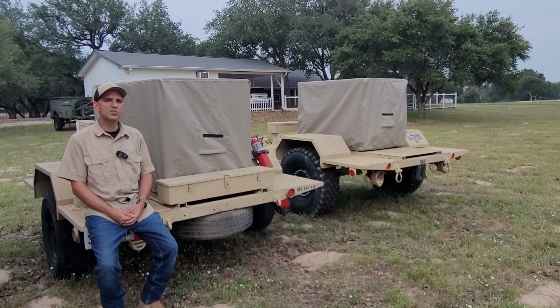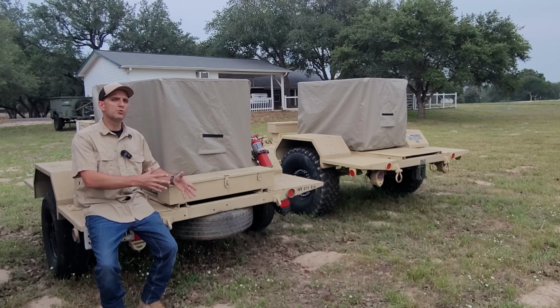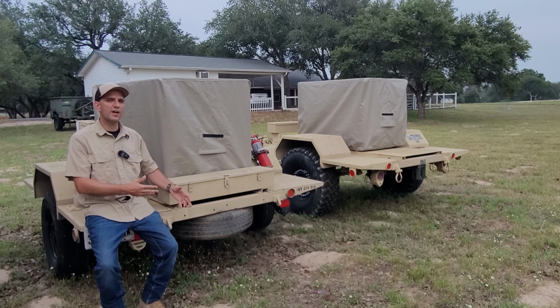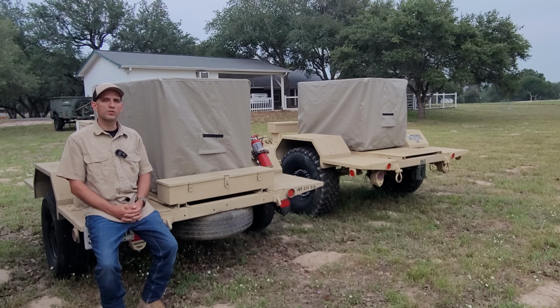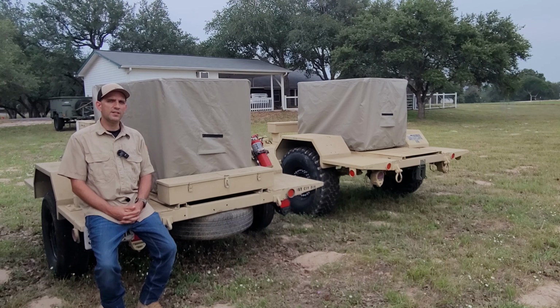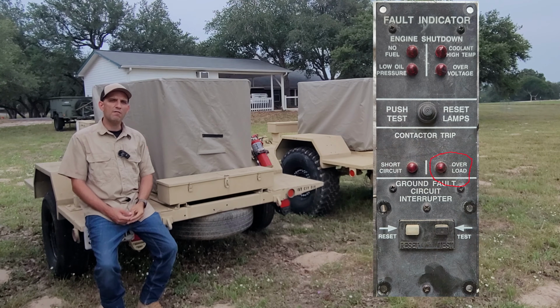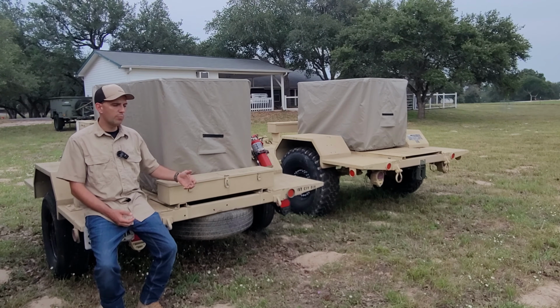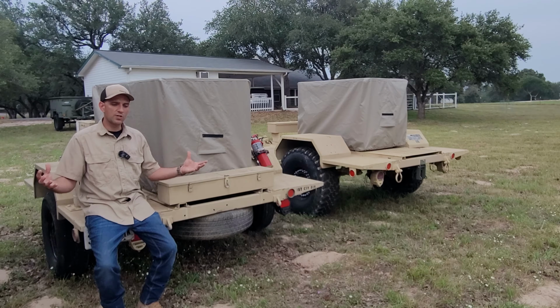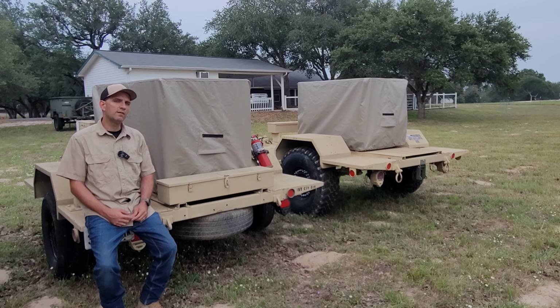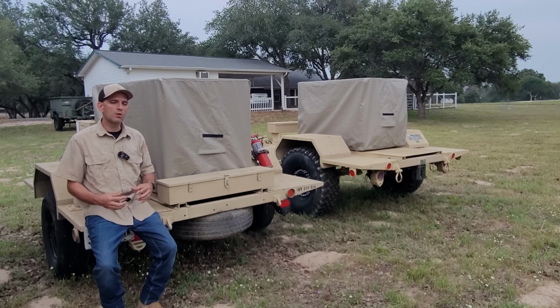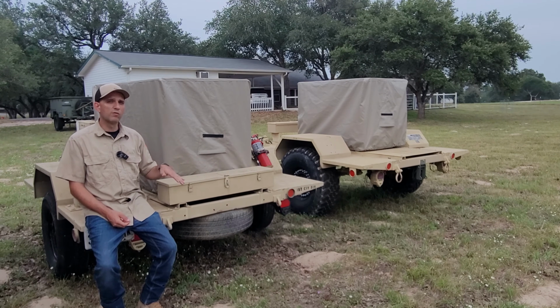All of those things together make it really safe for the most uneducated end user of the product, and also to give you that little bit of extra power out in the field for those who do know what they're using. But what I also mean about overloading the generator is there's the fault panel, and part of that fault panel is overload. If you put too much load on your generator, that overload fault is not going to trip and automatically open up the contactor that puts power out. It's actually just gonna bog your generator down, and it probably won't stall out, because I've done it. This is coming from experience. It's just gonna make the engine sputter, like barely run, almost like it doesn't have enough fuel. It's really bad for sensitive electronics. It'll just continue to run like that, so don't overload your generator in that sense.